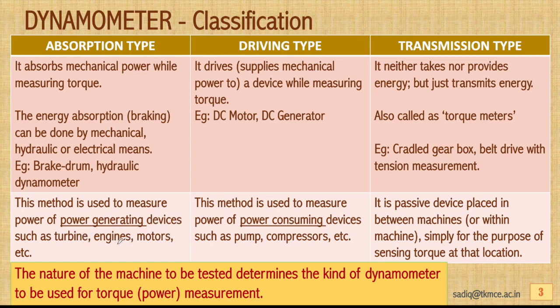Driving type dynamometers drive or supply mechanical power to a device while measuring the torque. Examples include DC motors or DC generators used as driving type dynamometers. This kind of dynamometer is used to measure power of power-consuming devices such as pumps and compressors.